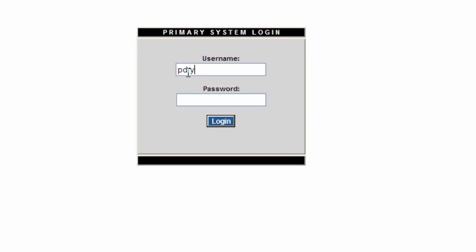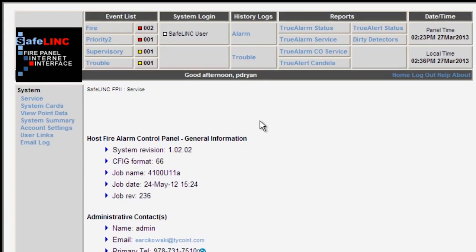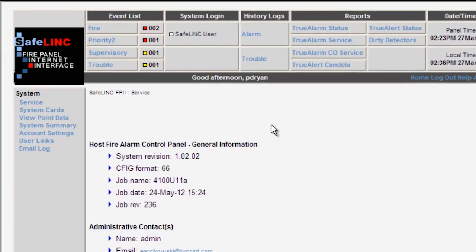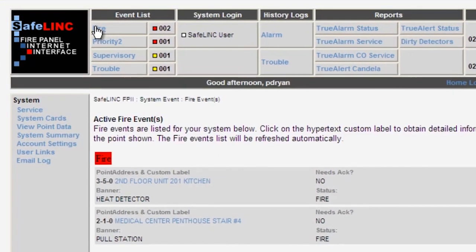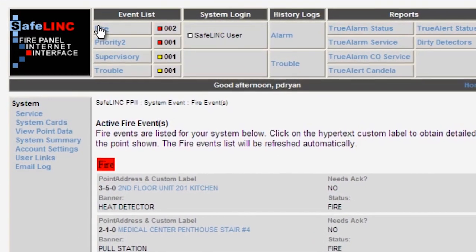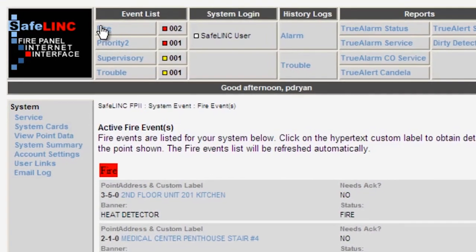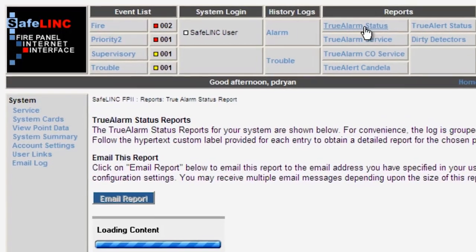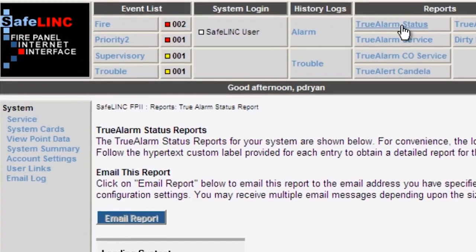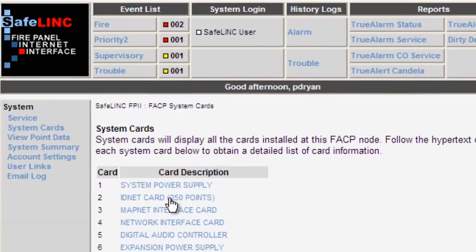The login that comes up is very simple and non-descriptive. This is by design and is a way of making sure that a hacker cannot easily identify the page as a link to a fire alarm panel. Once connected to the panel, users can view a display of active alarm, priority 2, supervisory, trouble events and counts, detailed point information similar to that available on the panel user interface, panel reports and history logs, true alarm service reports, and true alert addressable notification appliance reports, and the user can also look at the status of the cards in the panel.